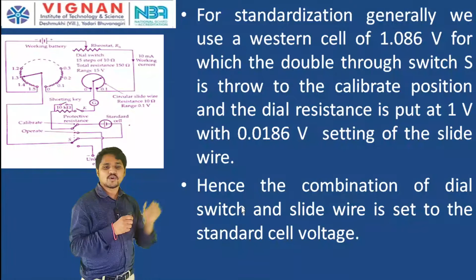Generally we use a standard cell of 1.086 volts. By using this, we can set the dial switch and slide wire combination to the standard cell voltage. So what are we doing in the standardization process? By connecting the standard cell, we adjust the rheostat, main dial and slide wire such that the galvanometer gives null deflection. That means the voltage drop across this slide wire and main dial is equal to the standard cell voltage. This process is what we call standardization. Once it is completed, we should not touch the rheostat.